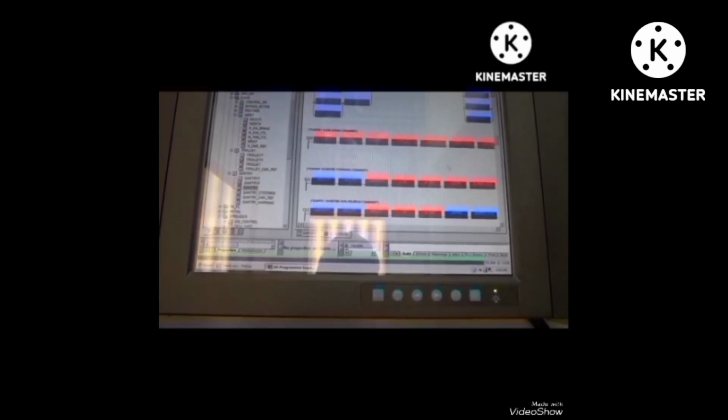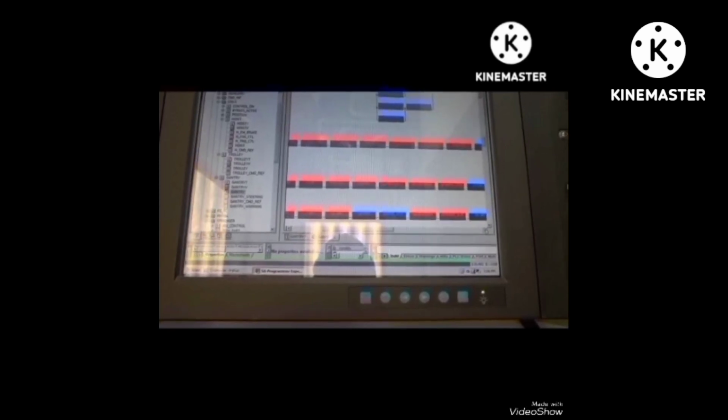See, there's one more RTG that was sent to me with a breakdown. This is a problem with the secondary. I'll open the program. There's a problem with the gantry. It has a problem with this anti-collision. This RTG has four anti-collision switches.